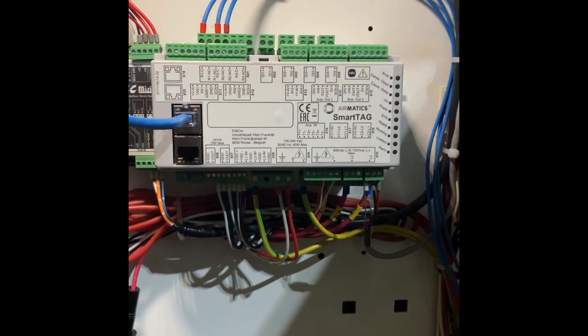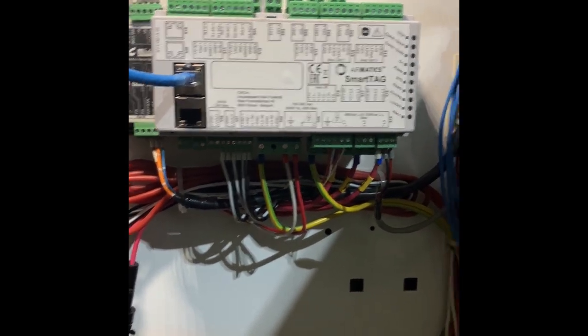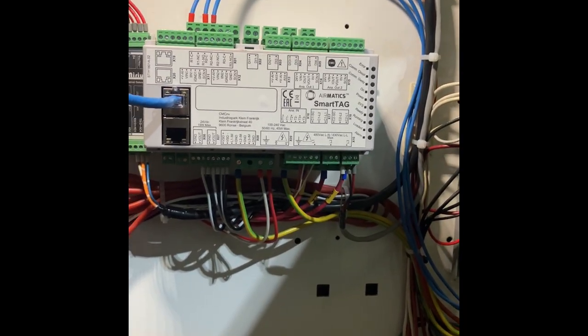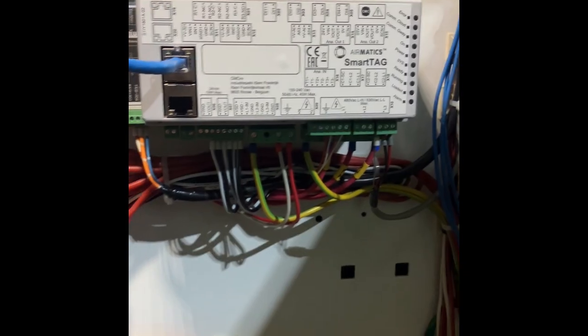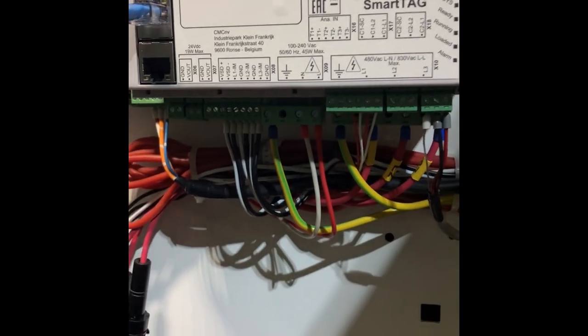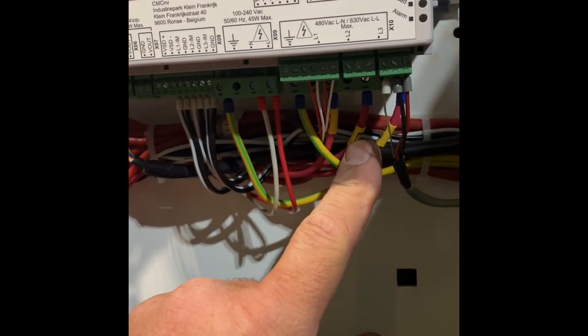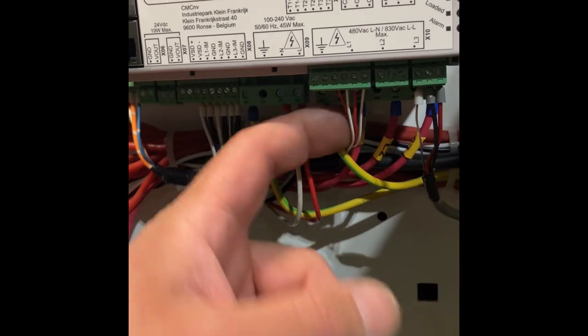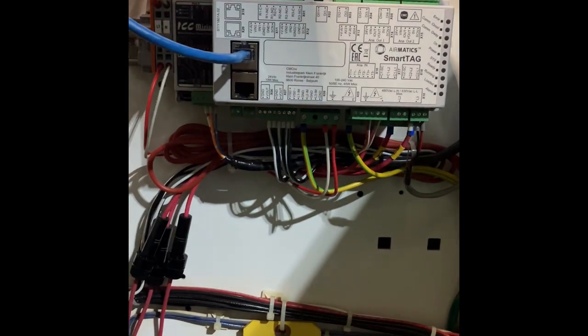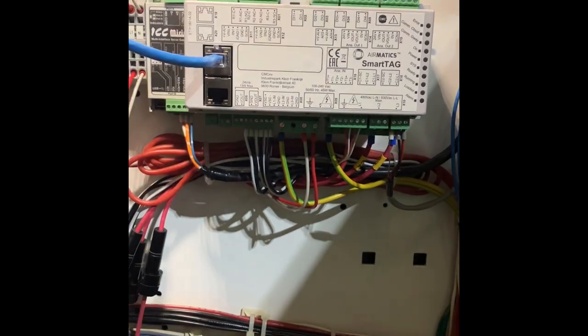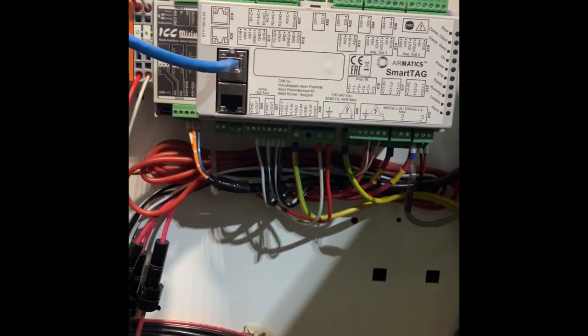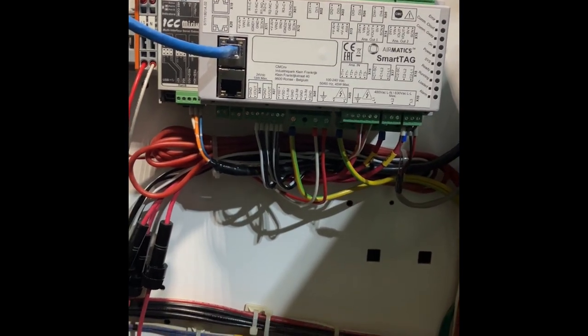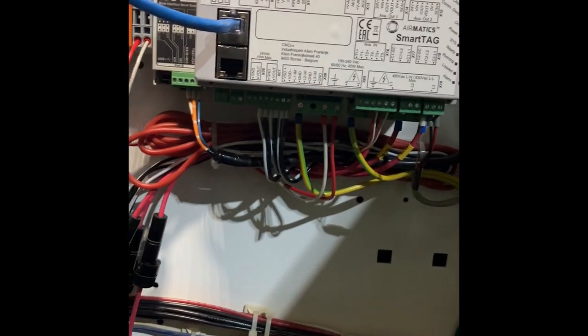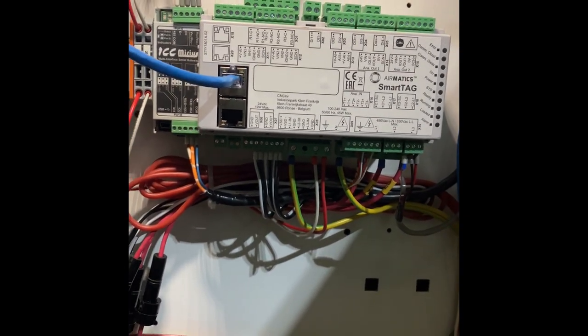All right, compressed air friends. So this smart tag for the Sullair Supervisor Controller is all wired in, and it's pretty much the same as any of the other ones, really. We've got our CTs here, 120 in, 480 coming in here. There's our 2 temperature probes for ambient and motor, and then we have our digital controls up here. This is basically to control the loading and unloading of the machine, and all other information is coming in via the serial comms.